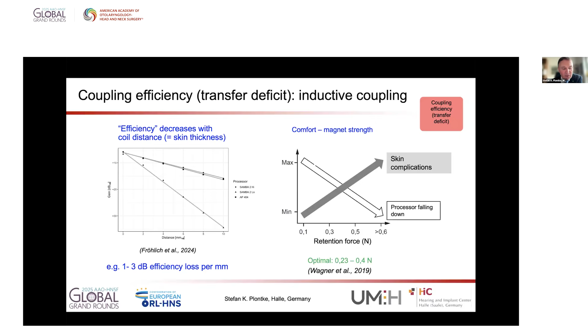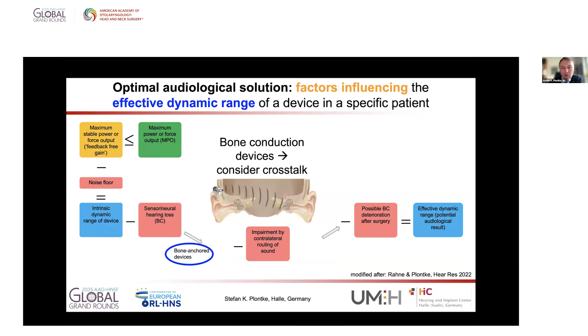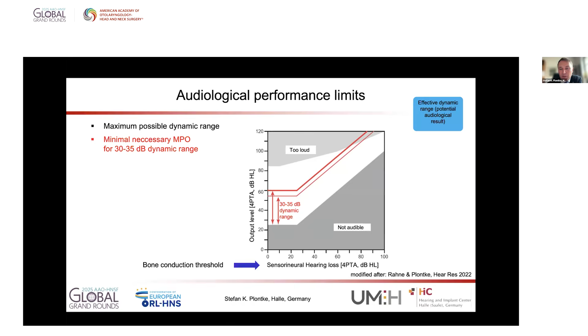As I mentioned already, for bone conduction devices, we have to consider crosstalk. If we fit an ear with a bone conduction device with a very poor bone conduction threshold and the other side has a normal threshold, we usually cannot crank up the device as much as we would to get the amplification, to get the gain, because we have crosstalk to the other side that will influence speech understanding and also directional hearing. So if we summarize this, if we look at the limits due to the bone conduction threshold, the sensory hearing loss, and then the maximum power output of a device, we get this maximum possible dynamic range. And if we aim for a 30 to 35 dB dynamic range for a good speech intelligibility index, the red line would now indicate the parameters that are necessary in the devices.